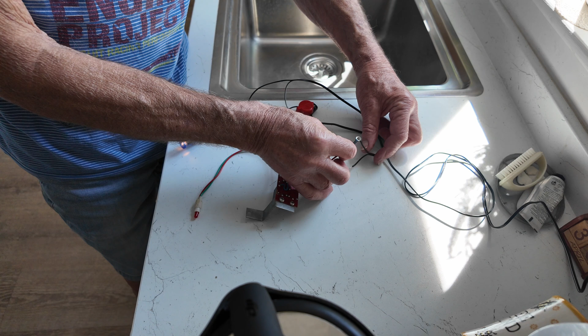This switch here, which came off a lawnmower, that simulates the oil pressure fail switch. So when the engine's running, that should be disconnected. When it's stopped, it should take this yellow wire to earth. The engine has a 12 volt auxiliary circuit, which the circuitry here uses when the engine's running. This wire becomes live from the auxiliary battery charging circuit. So we simulate that by sticking those two wires together.